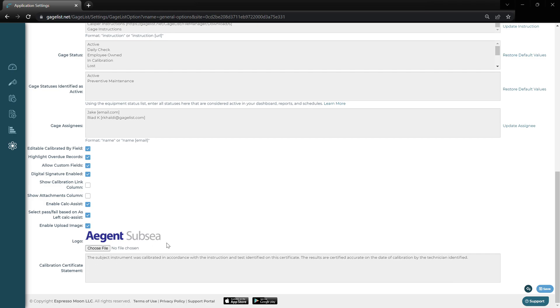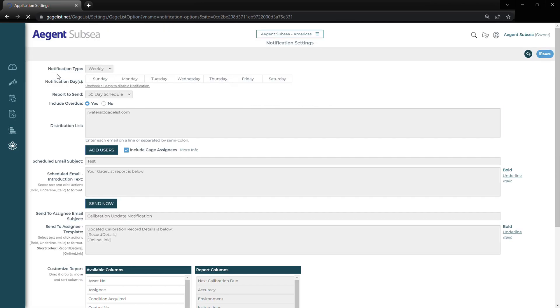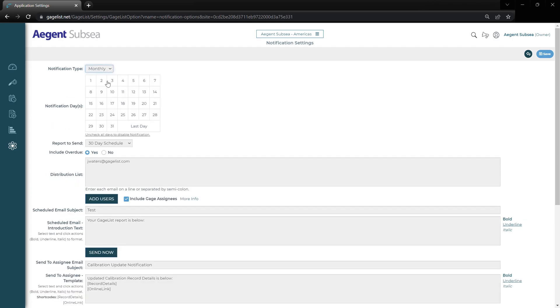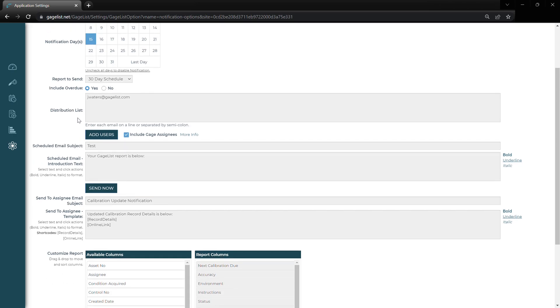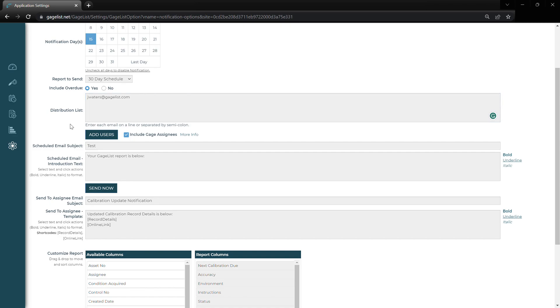Below that, we can customize our calibration certificate statement. Next, we have our notification settings. Here at the top, we can choose the type of notifications that get sent out, whether it be weekly or certain days of the week. We can also choose a monthly option, or any variations of days we want for the notifications to be sent out on. We can also choose the report to send — anything coming due in the next seven days, all the way to 180 — and we can choose to include our overdue gauges. Here we have the distribution list. The emails entered into this list will receive notifications for every gauge coming due in the system. Simply add a new email on a new line and they will start receiving emails for this site.